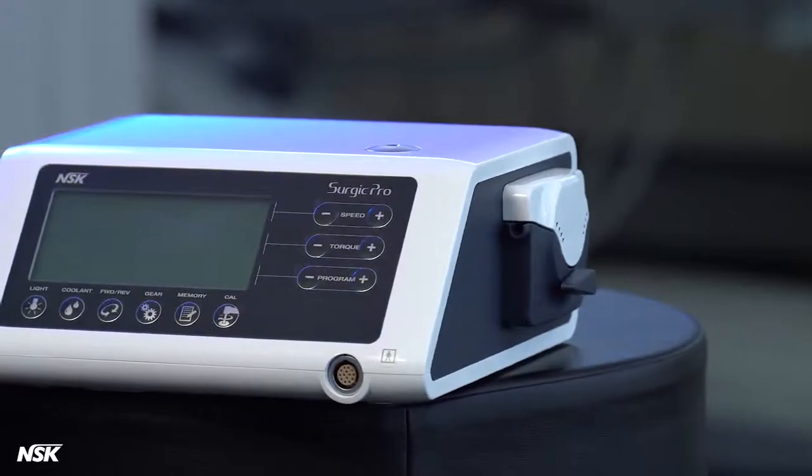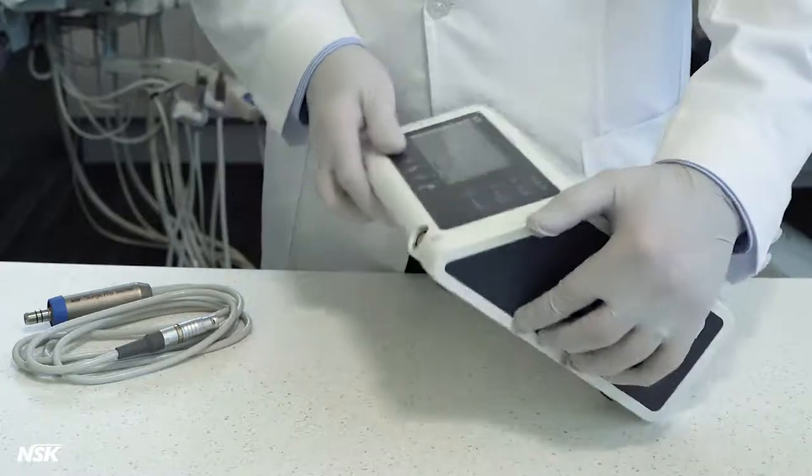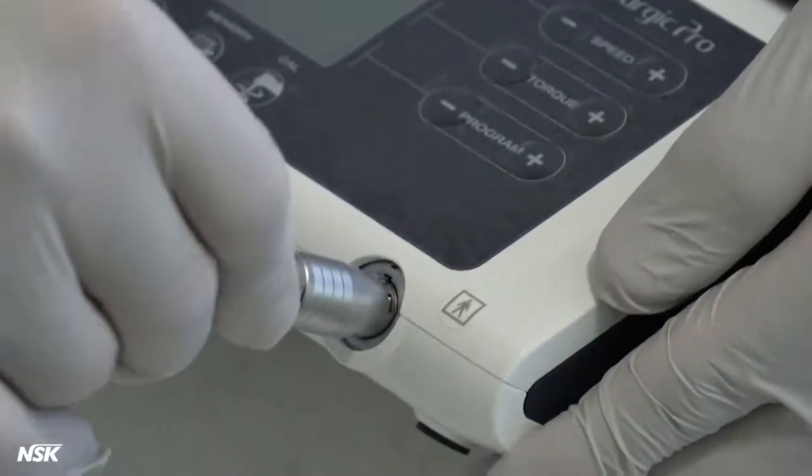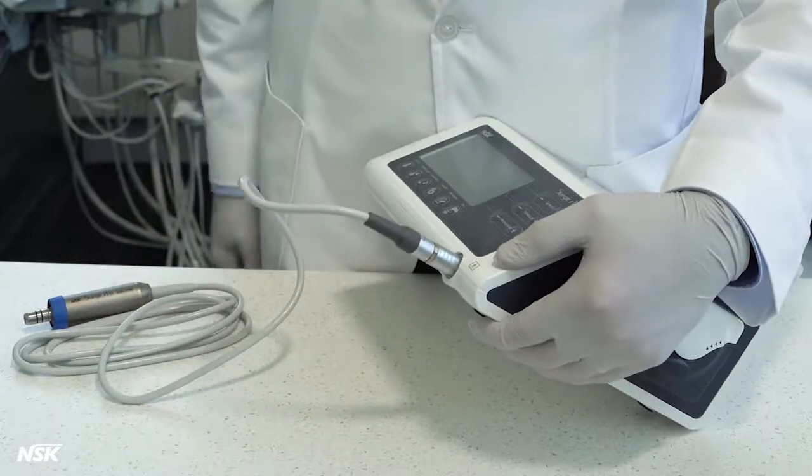Now let's move on to setting up your Surgic Pro. Installation: Connect the motor cord by aligning the marks on the cord connector and the connection on the control unit. Push in the connector until you hear a click. Slightly pull the cord to make sure it's locked in place.